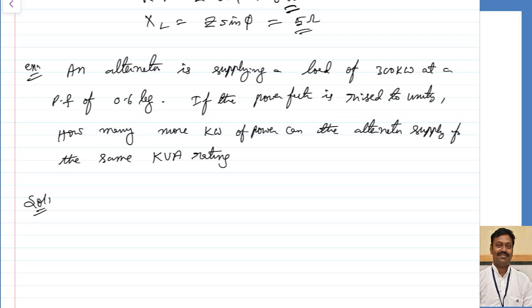The insulation depends on voltage, and the losses depend on the current passing through the circuit. That is why the rating of any machine is always given in kVA or volt-amperes, never in kilowatts. The rating depends only on heating and insulation strength of materials. For a given kVA rating, the machine can supply more kilowatts of active power if the power factor is higher.